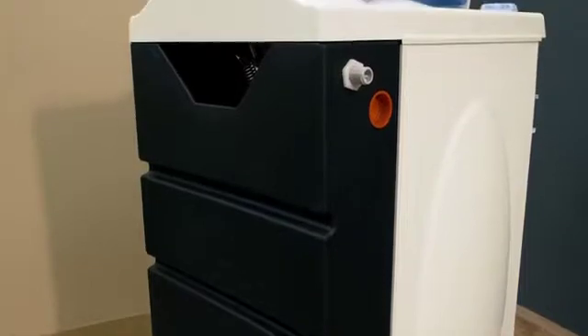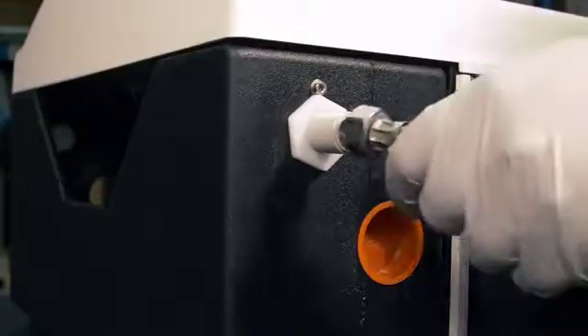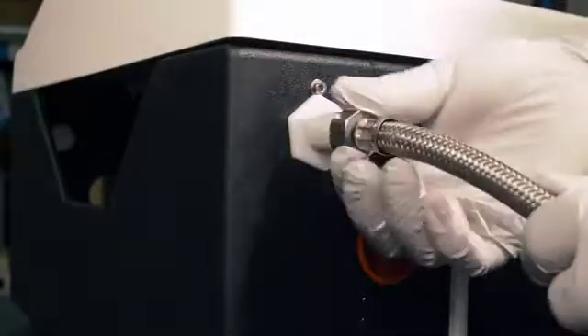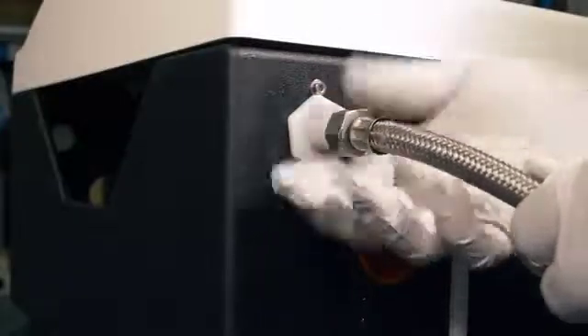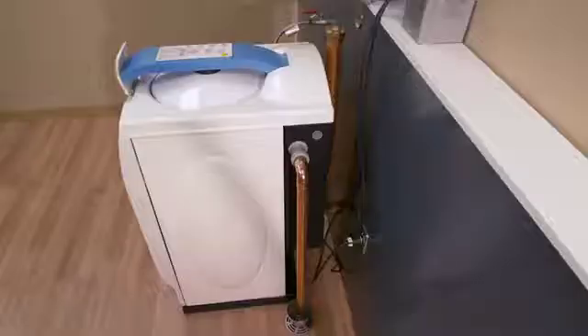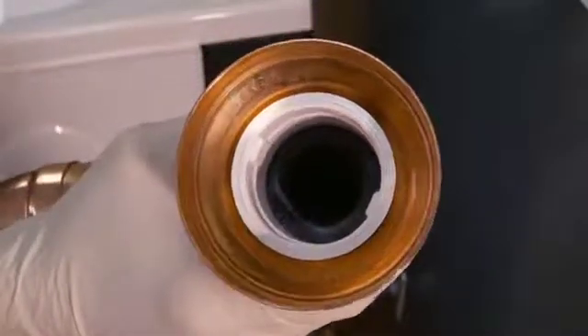Vortex has a built-in clean water reservoir that it draws water from during its cycle. In the event of a failure of the fill valve, provision for overflow must be made, either routing the water to a floor drain or by connecting to the wasteline using a tundish and check valve.